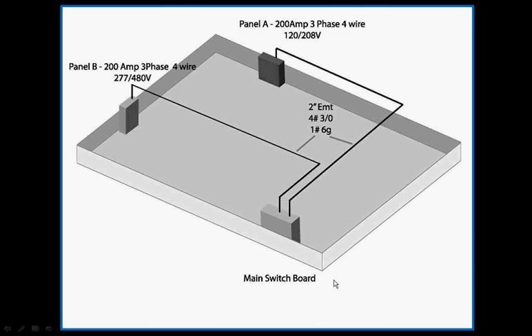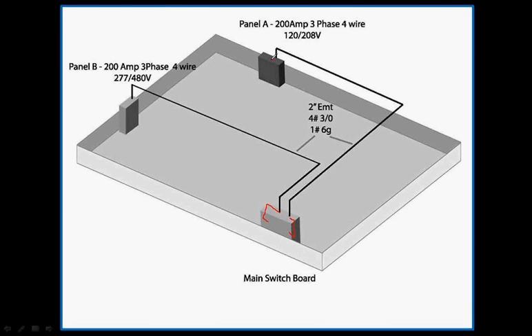The third thing I'll explain with a 3D drawing is wire makeup. Wire makeup is the length of wire it takes to extend past the end of the conduit to go to the termination point. In this case, the wire would have to go out of the end of the conduit and terminate on the circuit breaker or landing lugs in the panel. We must determine that length of wire to capture the cost of extra wire required. This extra wire length for makeup will be entered into Red Rhino using the conduit wizard.